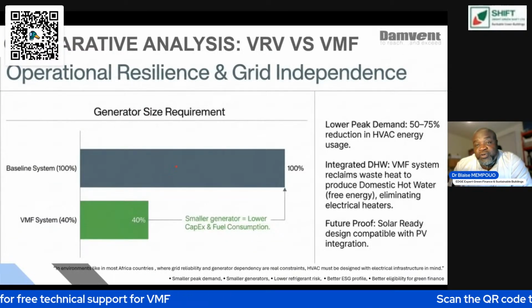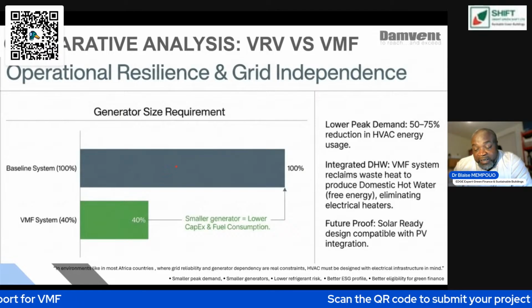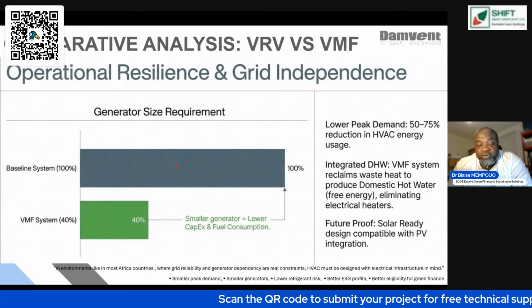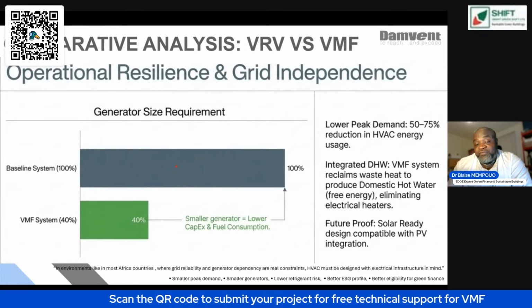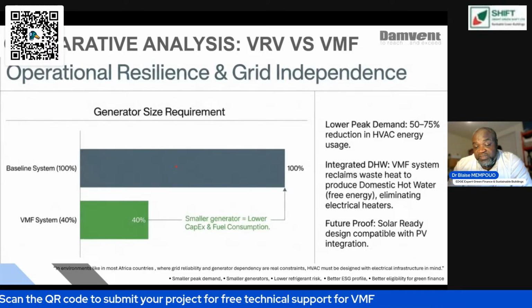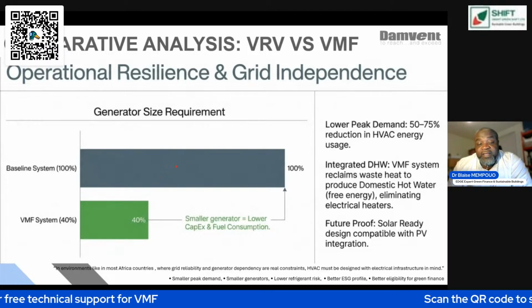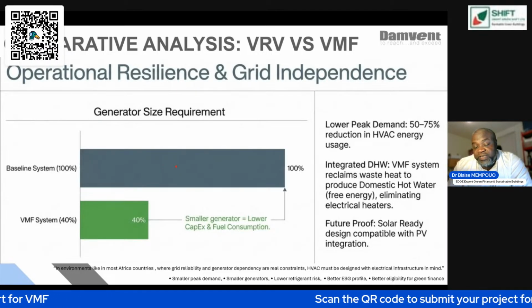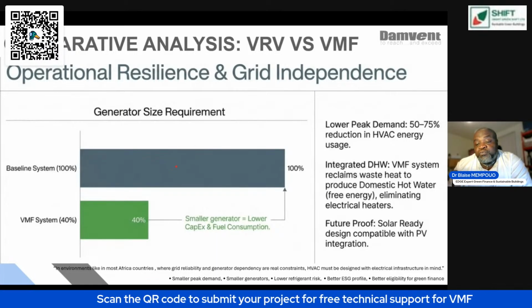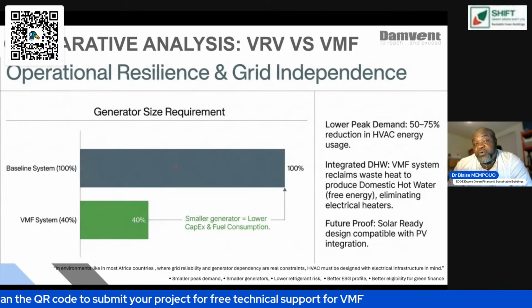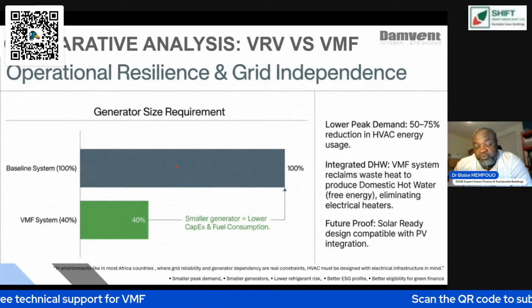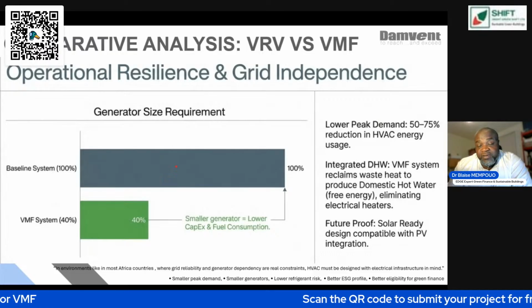HVAC must be designed with the electricity infrastructure in mind, so smaller peak demand is better. If you have small peak demand, it means you can easily install a PV system, or put in a smaller generator. Also, having a low risk refrigerant is much better because it gives you a better ESG profile and better eligibility for green finance, since you reduce your impact on climate. That's another advantage the VMF can bring over a conventional system.